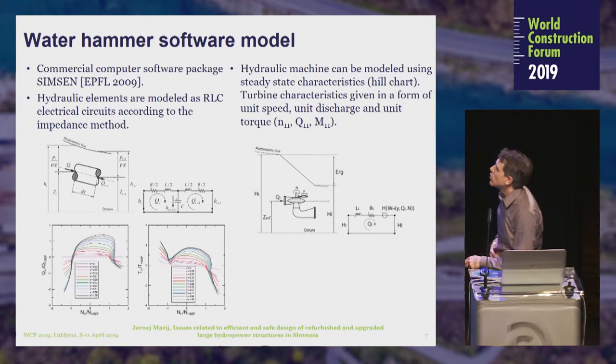The water hammer software model we use is a commercial software package developed in Switzerland — SIMSEN — where hydraulic elements are modeled as RLC electrical circuits according to the impedance method. We can see here the model of a pipe and the corresponding electrical model. For hydraulic machines, we model using steady-state characteristics, also known as hill charts, where turbine characteristics are expressed in the form of unit speed, unit discharge, and unit torque. We can see a hydraulic model of the turbine with its corresponding electrical model and a schematic of hydraulic machine characteristics.